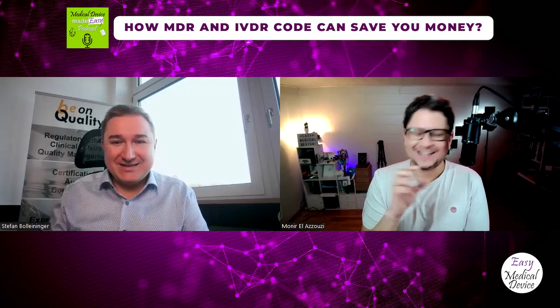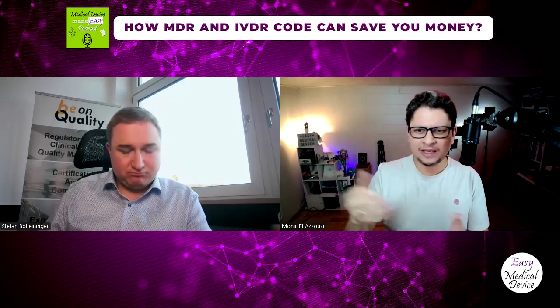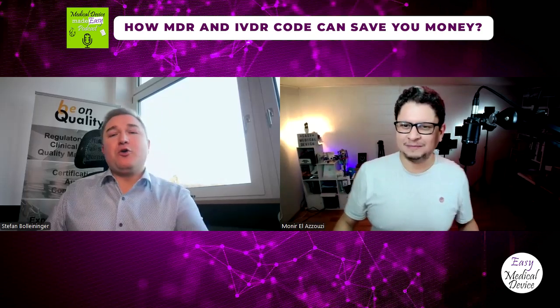It's a good tip here. You take the easiest product, which has the right MDR, EMDN, etc. code. You pass the certificate with that, the technical file, the audit, everything. And as the other products, the big ones, have the same MDR code, the same EMDN, or the same scope as what you had before, you don't add any new code or any new things. Then it's just a notification, it's just a few bucks to pay, and then you are including them inside.